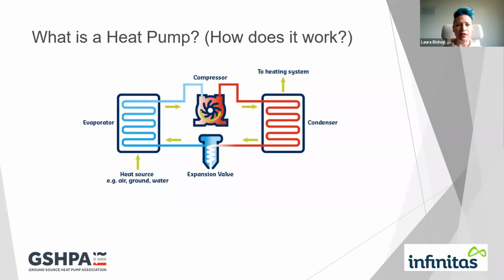What we've got going on here is the blue and red lines, that's refrigerant, and that's either a gas or a liquid depending on where we are in the cycle. Starting on the left-hand side, we have the evaporator, which takes in the energy that's free and available, whether that's air, ground, brine coming out of the ground, water coming out of the ground, the river, mine water, or wastewater. It's absorbing energy from outside. That refrigerant is then passing into the compressor, where it's compressed to high pressure.